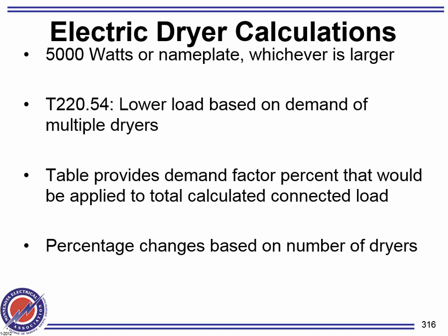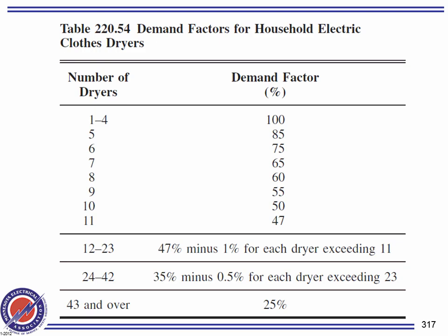Let's start with electric dryers. If you have an electric dryer, we use them all the time. Hotels and motels. If you have hotels, not hotels, apartment buildings. We have an apartment building, guys, and these are household electric, not gas dryers. If you have 11 apartments, and you're sizing the feeder that feeds all 11 apartments, then your derating factor is 47. How do you use it?